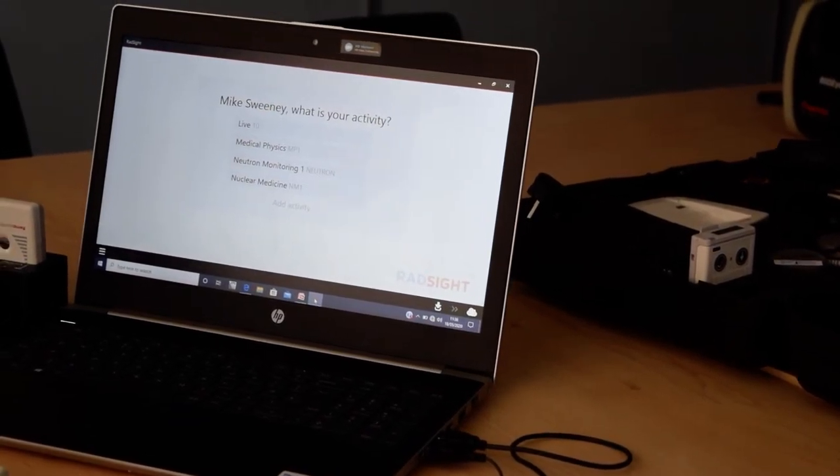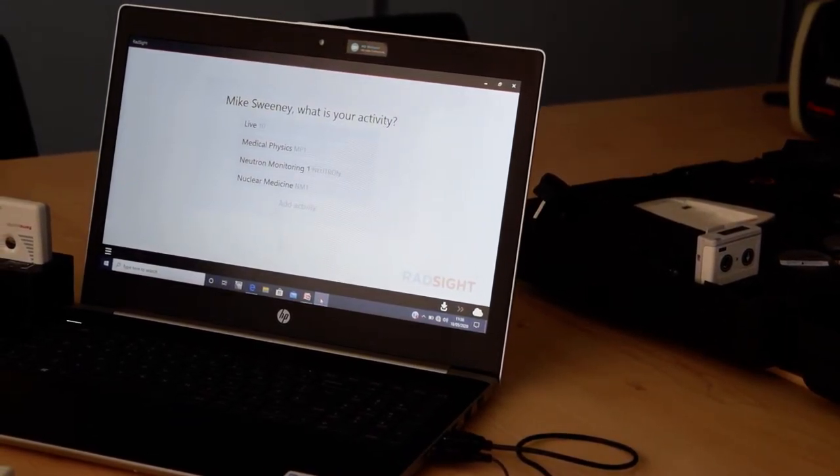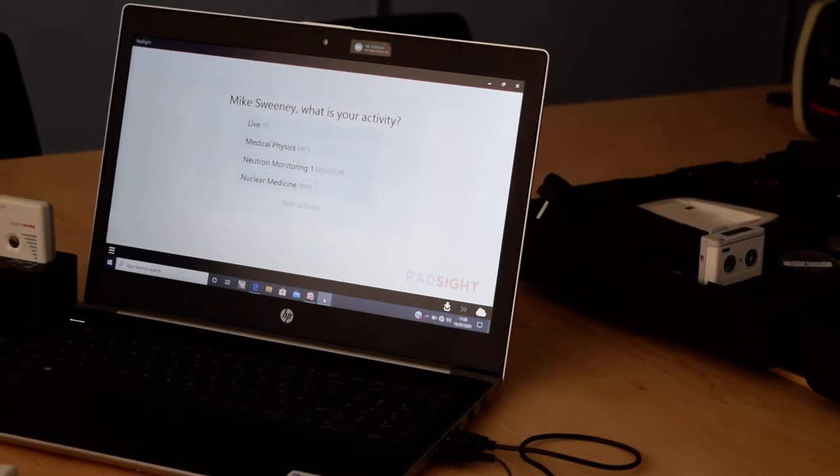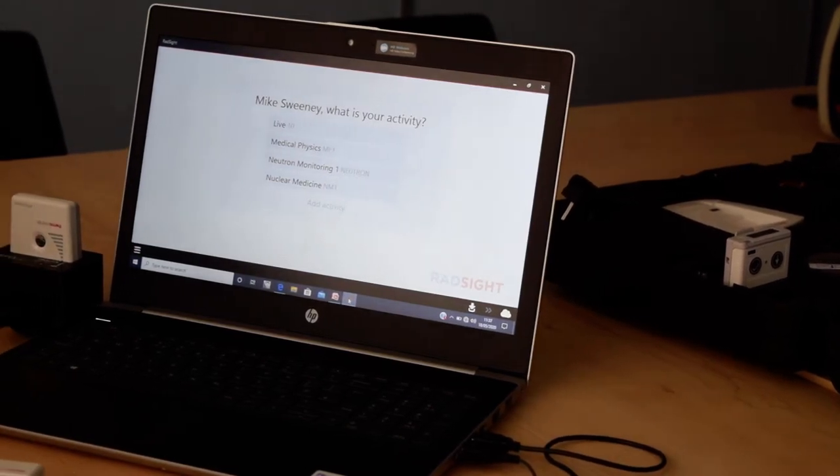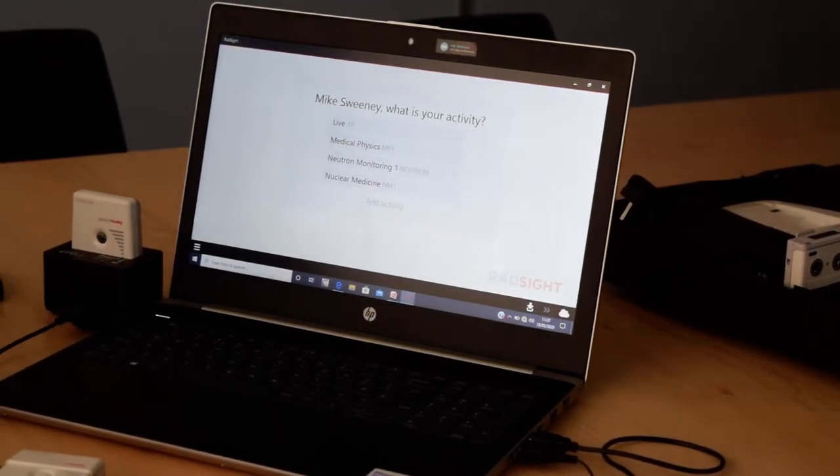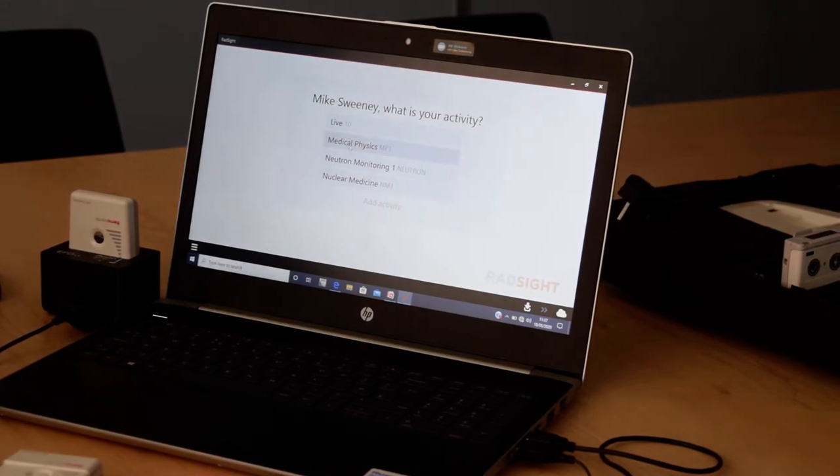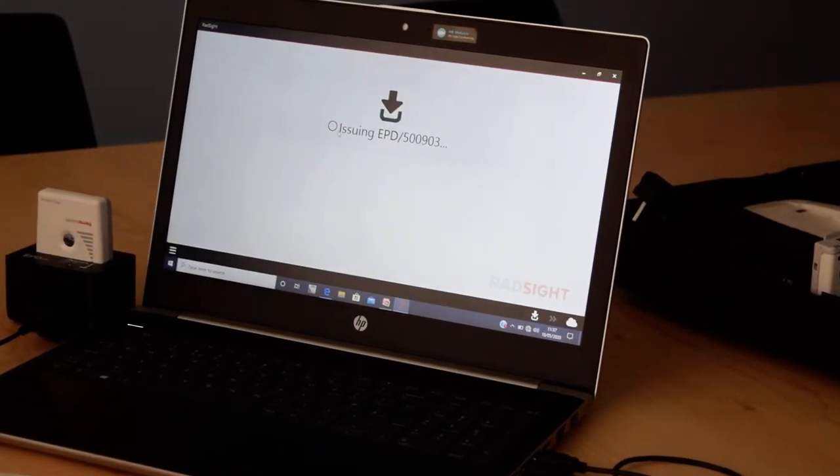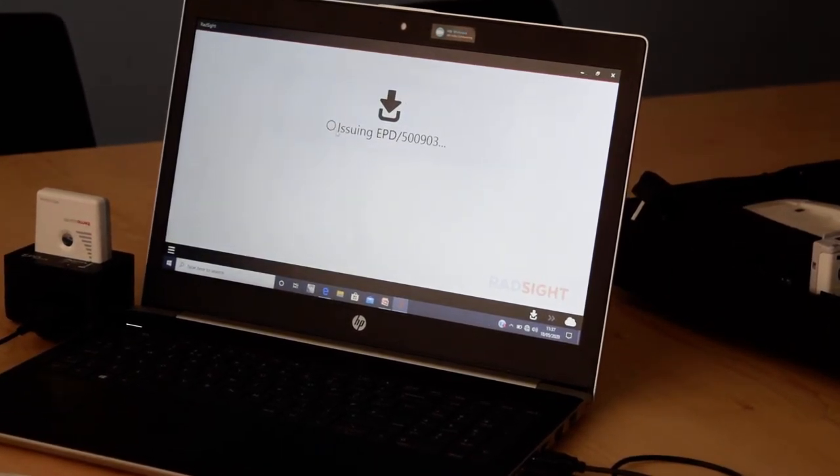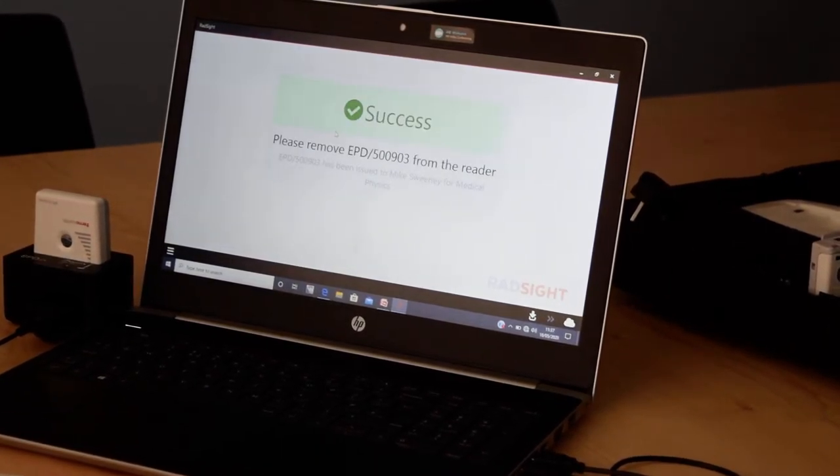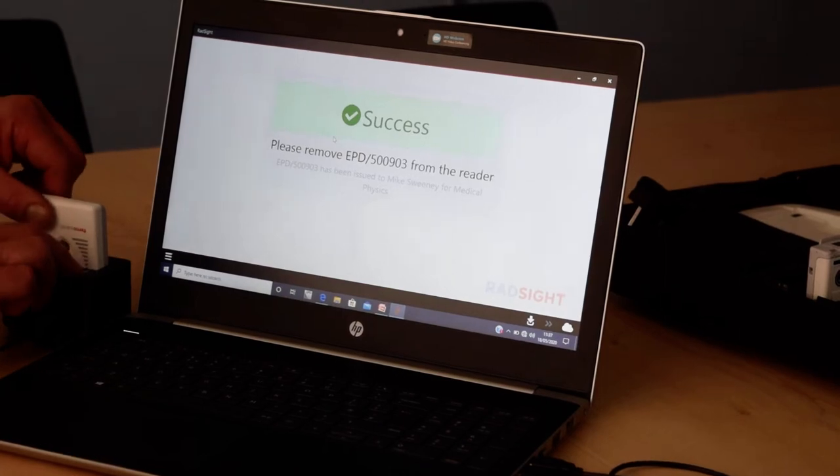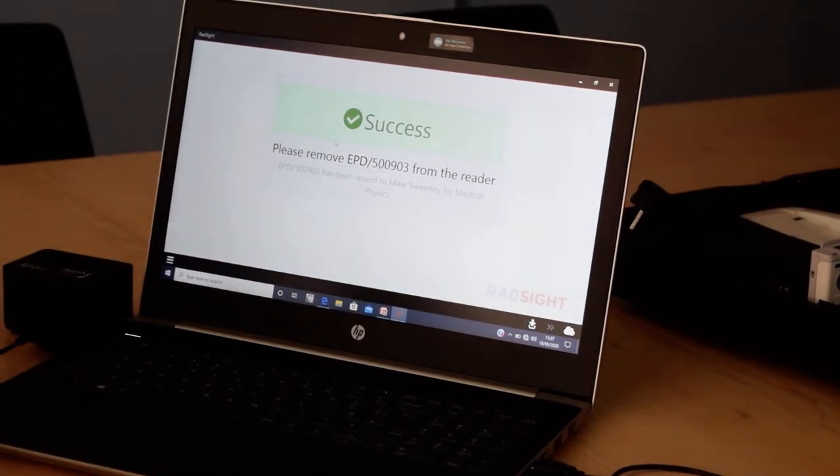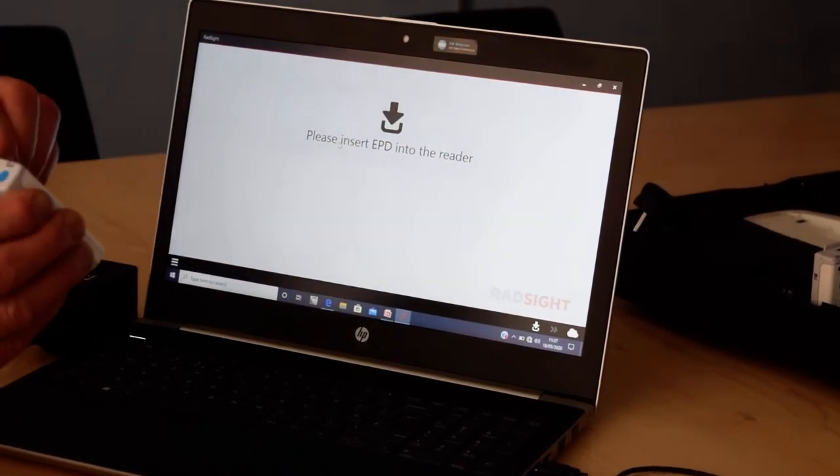Each activity can have preset dose and dose rate alarms. So I can now issue this one, for example, to the Medical Physics Department. It's now issuing the dosimeter. It takes a couple of seconds. Once you remove it from the cradle, it's zeroed the dosimeter.